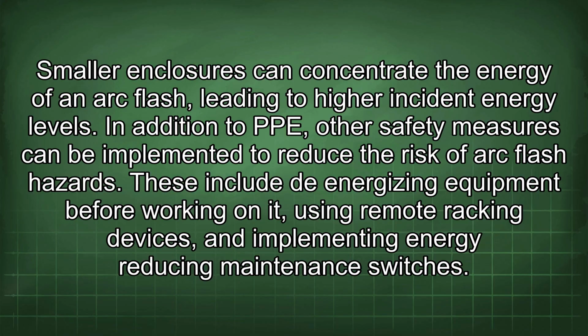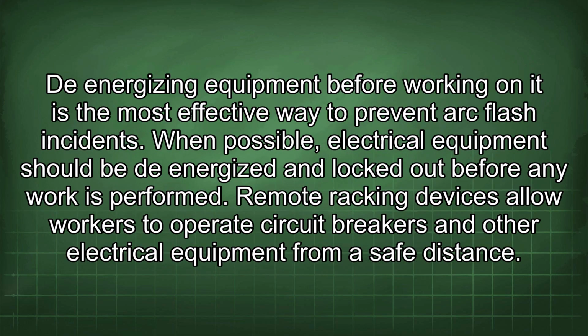In addition to PPE, other safety measures can be implemented to reduce the risk of arc flash hazards. These include de-energizing equipment before working on it, using remote racking devices, and implementing energy-reducing maintenance switches. De-energizing equipment before working on it is the most effective way to prevent arc flash incidents.